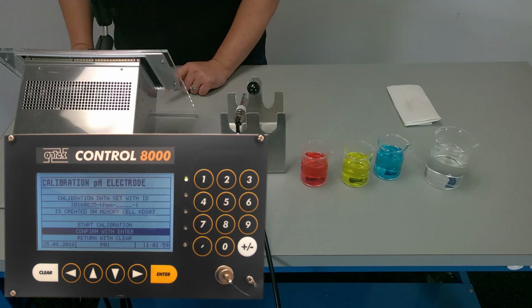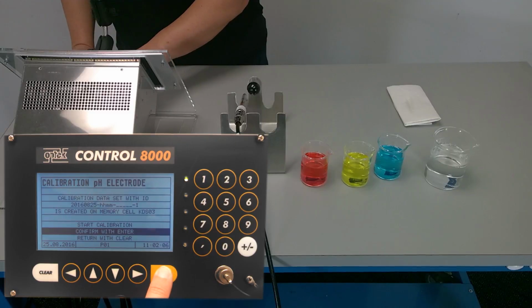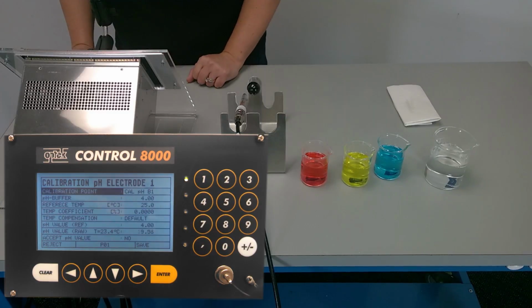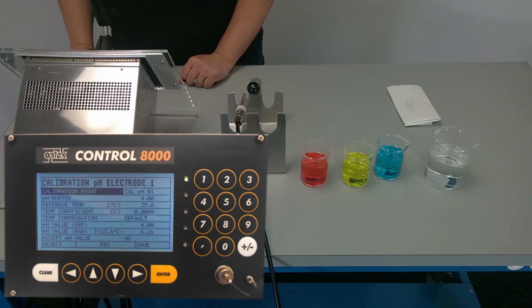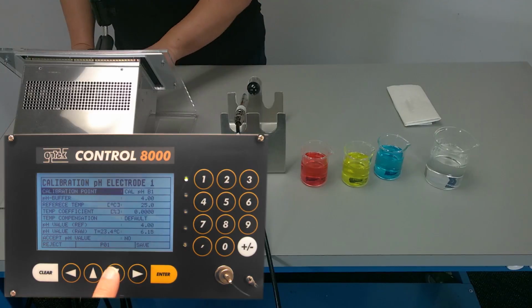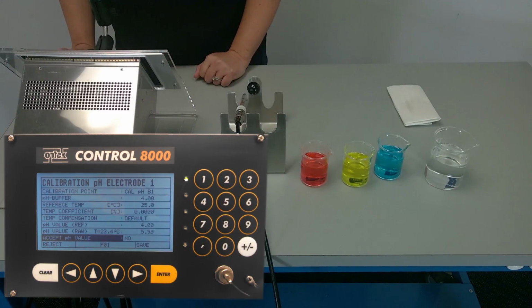The converter will assign a date and time stamp code to every calibration that's done. We will confirm with Enter to begin the calibration process. So our pH buffers that optek recommends are calibrating at a 4 and a 10. So we will start with our pH buffer 4. So to get everything ready, I will just scroll down to accept pH value.